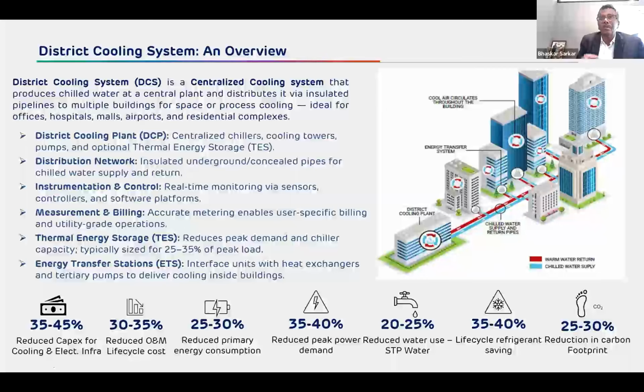So if we are using a commercial system, if we use conventional, then we have to use, let's say, 3000 TR of capacity, and say 4000 TR of capacity, and if we use DCS in place of that, we need about 70% less. So by design, if we have a thumb rule of 1 kg per TR, we are reducing the refrigerant consumption by 30 to 32%.